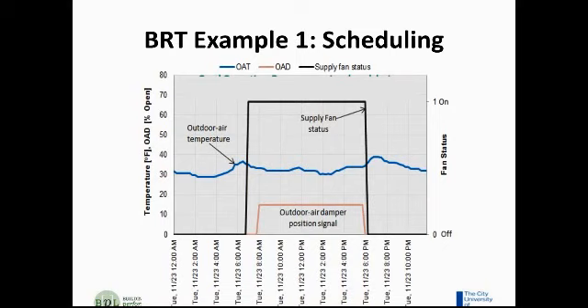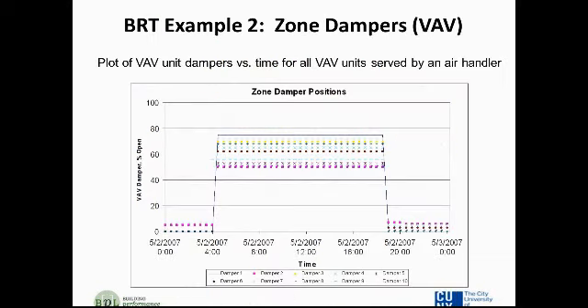Again, just a simple example of occupancy scheduling, looking at a trend chart. Here's another one that looks at the same thing. It's the exact same temperature profile, the exact same setup for the exact same building. But in this case, not only are we looking at the outdoor air damper position signal like we were before, but the dark line actually also looks at the supply fan status. So it tells us if the supply fan is on. In this case, we see that it's the same 24-hour period, the same temperatures outside, and the outdoor air damper position signal shows that it's open at minimum position for most of the day during the occupied hours. In fact, it's even closed during the warm-up period, during the first hour of warm-up when people have not yet arrived. So this is an example of good operation.